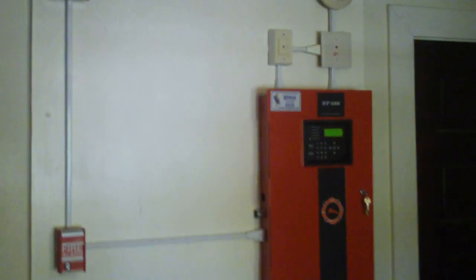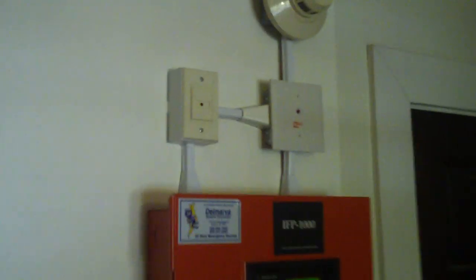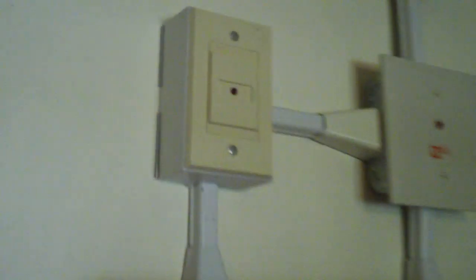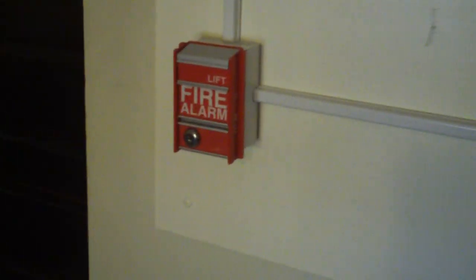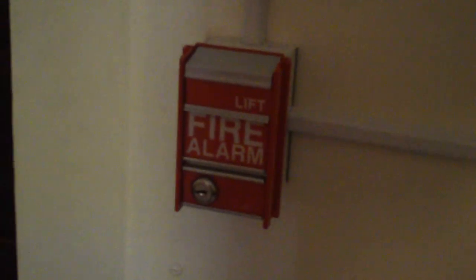As you can see, I've made a few changes to the system. I installed this smoke detector annunciator up here, and I also got a Silent Knight addressable monitor module, so now the panel can read this pull station as an addressable point rather than just a conventional zone.